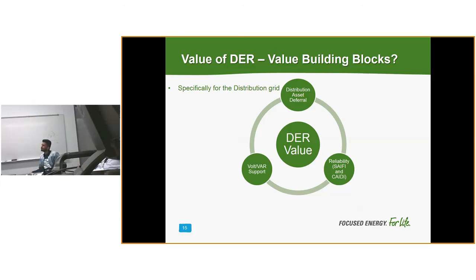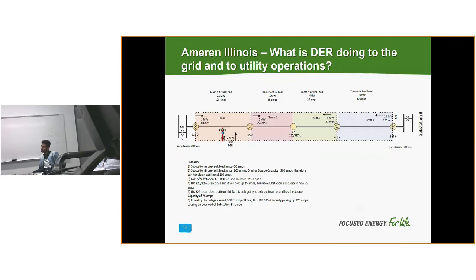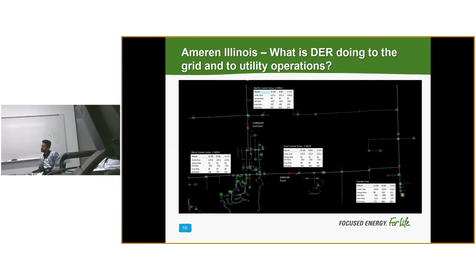Volt-VAR support: we talked about that scenario where we had voltage issues. You could think of this as an area on the distribution system that needs voltage support, an area where the voltage is extremely low naturally before you add DER. Instead of going in and adding a cap bank to help with that voltage, I say wait a minute, it cost me 30 grand to put a cap bank. If a DER can come here, there might be value to the DER that's cheaper than 30 grand, and I can compensate that developer with DER there to help during the hours I need voltage support.